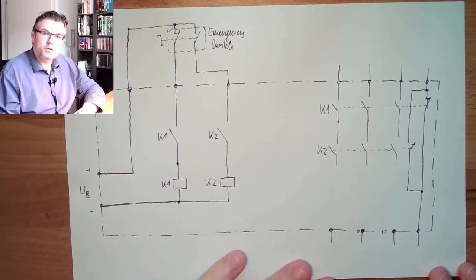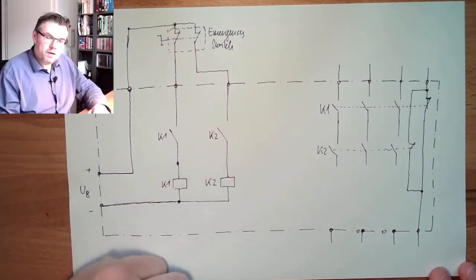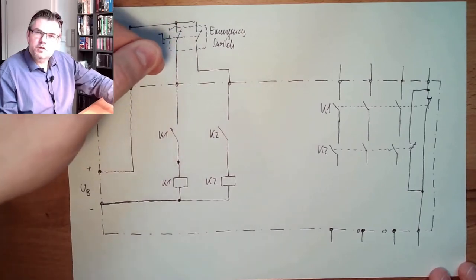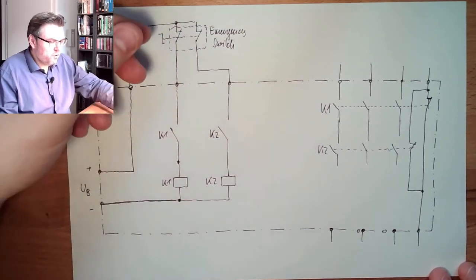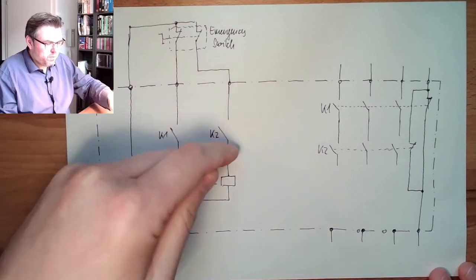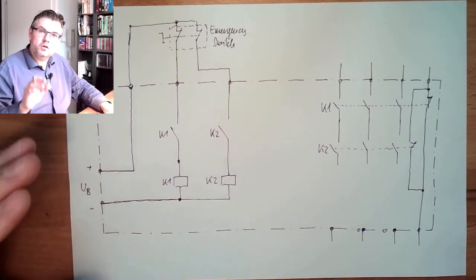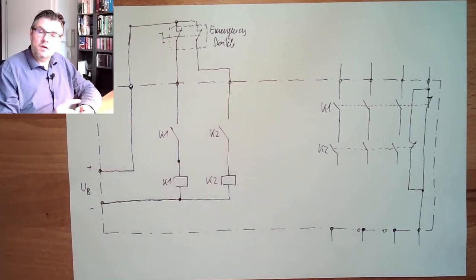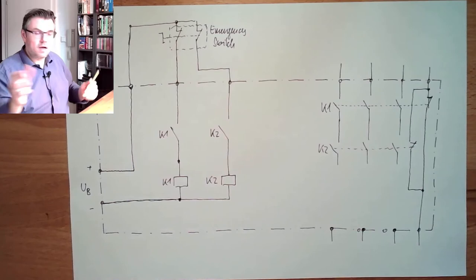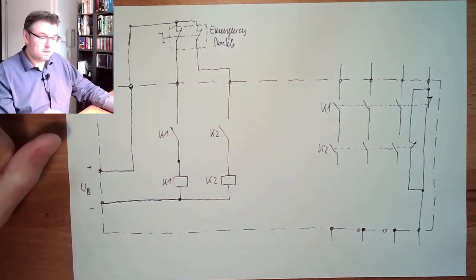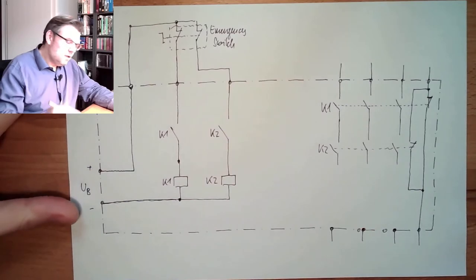Now I have an issue. How do we close them again? Just returning the emergency switch to its original position is not working, because these are open. This will not turn on. This would be stupid. I push emergency stop, then I release emergency stop, it's already starting? No, this should not be. We talked about this. We need a reset button.